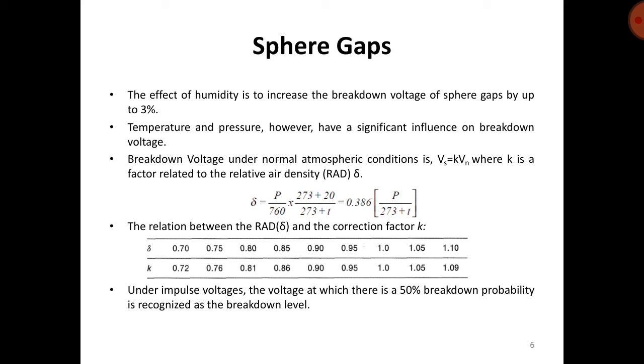Temperature and pressure, however, have a significant influence on breakdown voltage. Breakdown voltage under normal atmospheric conditions is Vs = K × Vn, where K is a factor related to the relative air density, delta. Small delta is equal to p/760 × (273 + 20)/(273 + t). So this is the equation for relative air density. The relation between the relative air density and the correction factor K is given in this table.